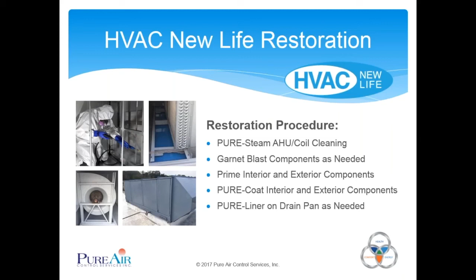We also have a product called Pure Liner, very similar to Pure Coat, that we can apply to the drain pan as needed. If you have a stainless steel drain pan, there's no need to coat it. But if there are pinholes or it's gotten rusty, creating spots where microbes can sit and grow, we'd definitely want to do that as part of New Life. We can also repair fairly big holes and patch it so you wouldn't have to replace a drain pan entirely.